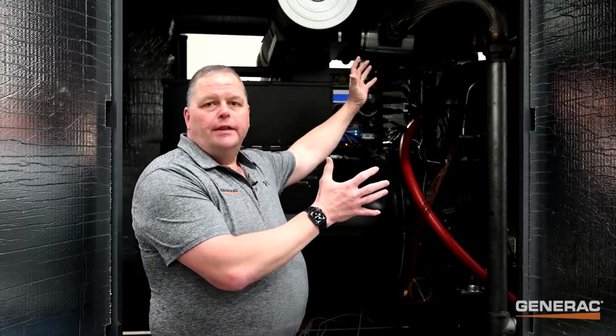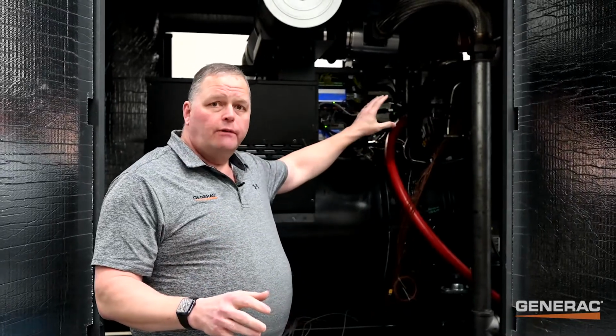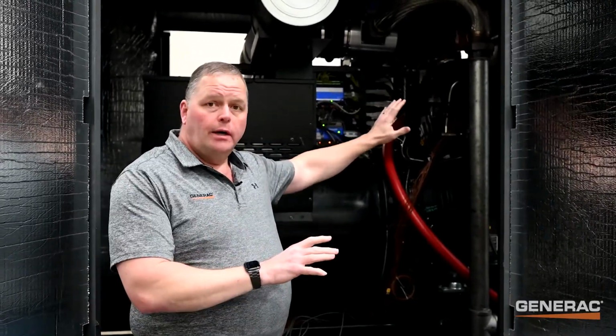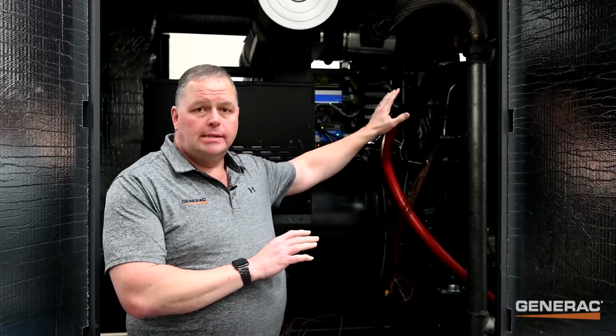So, what does all that tech get you? It gets you fast starting times, fast transient response. It gives you operation that rivals a diesel generator set. Why do you care? Because all too often in the past, we used diesel generators in situations where we didn't have the confidence in natural gas systems that we have now. So you talk about life safety systems, NFPA 110 type applications where you need to start. We have a patented fast start fuel system on here. We can start this generator up and ready to accept load in under 8 seconds.